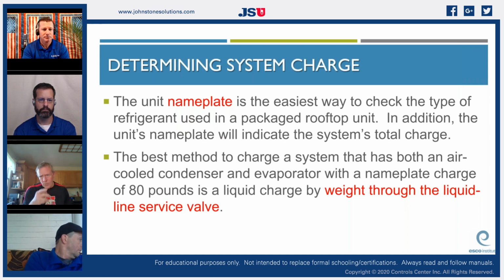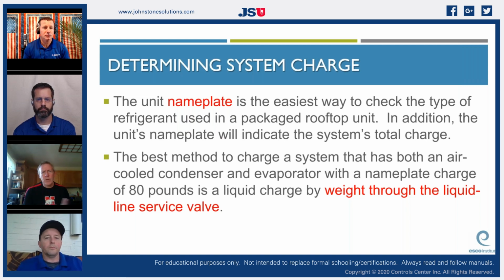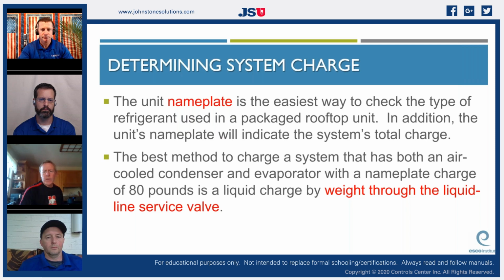And a lot of times when you go to Brian's class and work with these VRVs and stuff, we don't top a lot of charges off, especially with mini splits. If we find a leak, we recover it, we repair it, we weigh the factory charge back in via the nameplate. That's right. And the best way to put a charge in any system is to pull it into a vacuum, added as a liquid through the liquid valve.